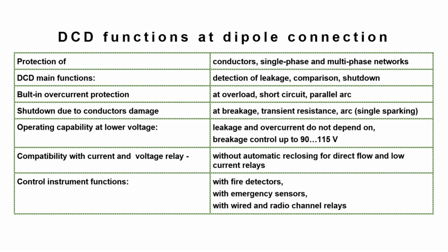Let's summarize with the table of functions, which shows a significant addition to the protection capabilities. In fact, it is proved that with a dipole connection, one standard device replaces an entire control cabinet. It overlaps the characteristics of known AFDDs and can protect individual conductors as well as single-phase and multi-phase networks.